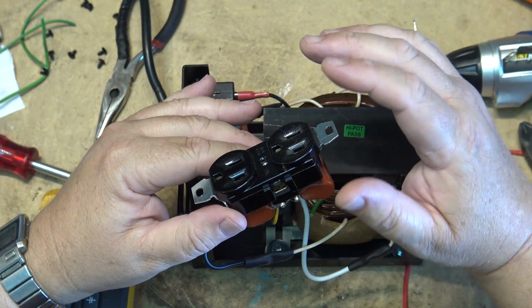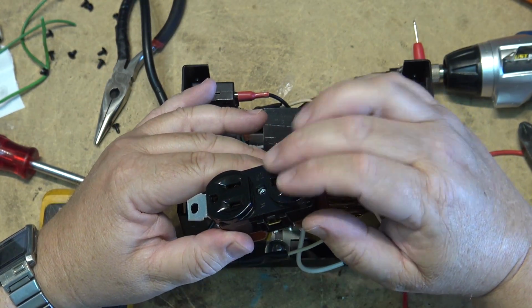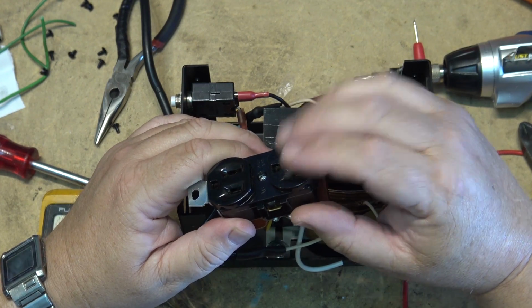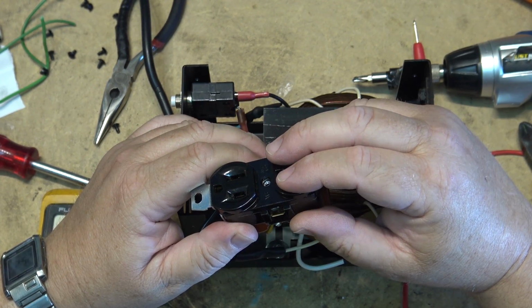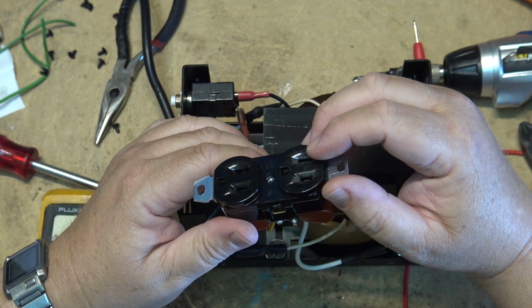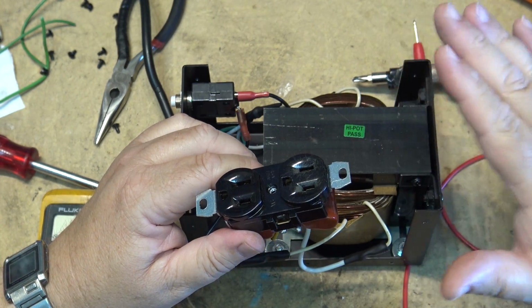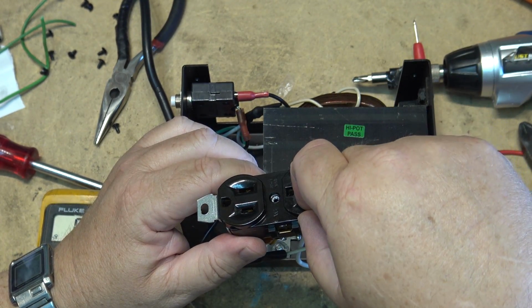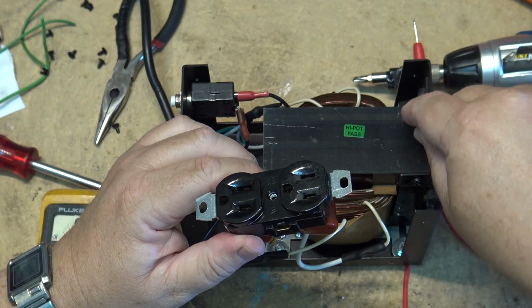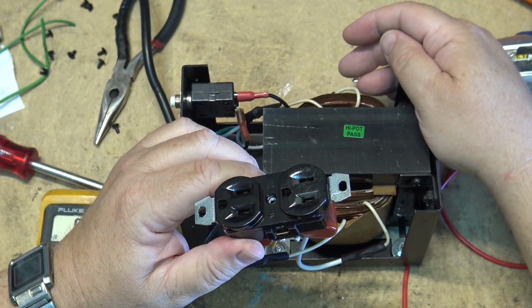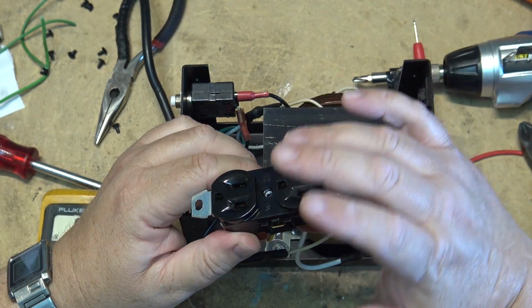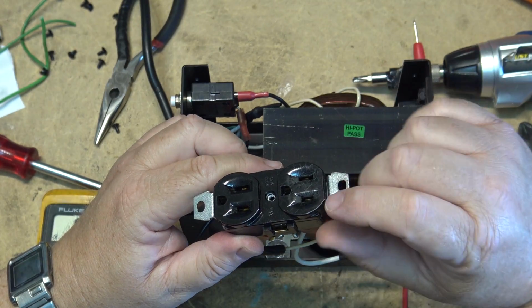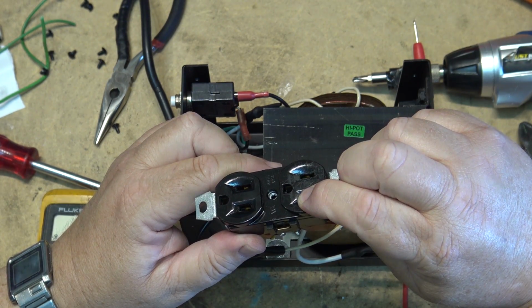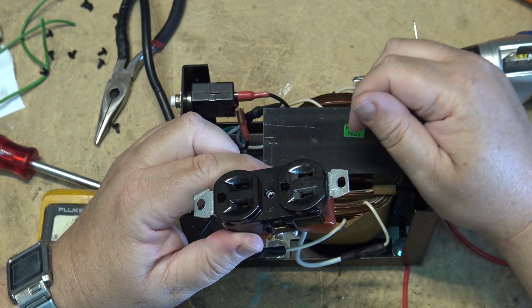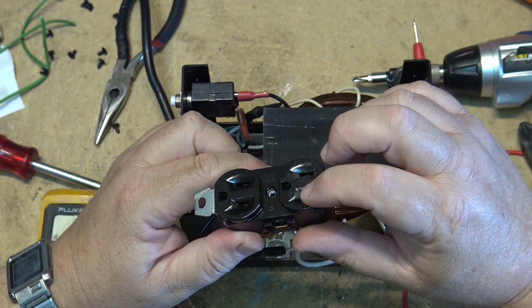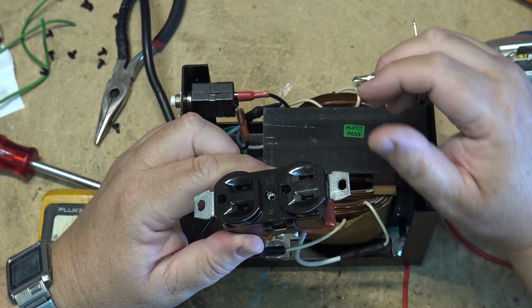The whole idea behind an isolation transformer is that both of these terminals float with respect to ground. So if I were to short between ground and this pin, nothing would happen. If I were to short between ground and this pin, nothing would happen. Why? Because the transformer secondary allows it to float. If I were to ground out the hot pin, guess what happens to the other pin? It becomes the live pin. If I ground out this side, the neutral side, the hot pin becomes hot.